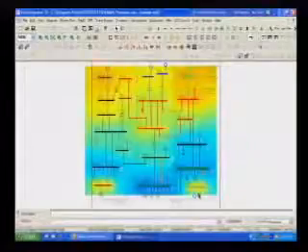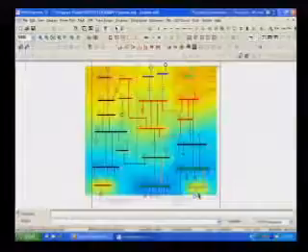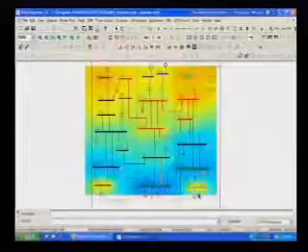You can see that the upper part of the network in the single line diagram has very high voltage, since the diagram is mostly red and orange. On the lower part of the diagram, the color is very cold. We may potentially have low voltage violations. You can make these kinds of representations either through the text or diagram.